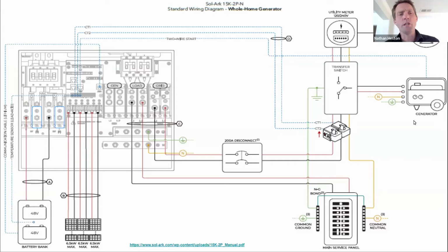But John, wouldn't the inverter itself know through the two-wire start signal that it has started up the generator in the event that those batteries are low and it needs that power? Complicated systems are complicated. It's not so much that the generator isn't starting up to charge, it's that you also have a large, say, AC coupled source trying to backfeed the load, and you're not implementing a load sink or anything to have that surplus power be managed. So it really gets into issues when you do microinverters with generator design, needing to put the generator for one reason or other onto the grid side of the inverter.